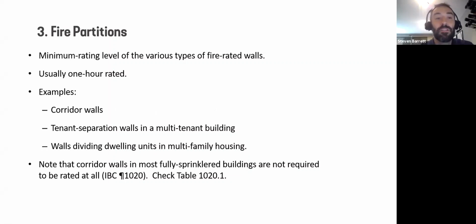Now, fire partitions are the third and the least rigorous type of assembly. And they're typically 1 hour rated. And you'll find these often in corridor walls in residential buildings or non-sprinklered buildings, tenant separations in multi-tenant buildings like open malls, and walls dividing dwelling units in multifamily housing.